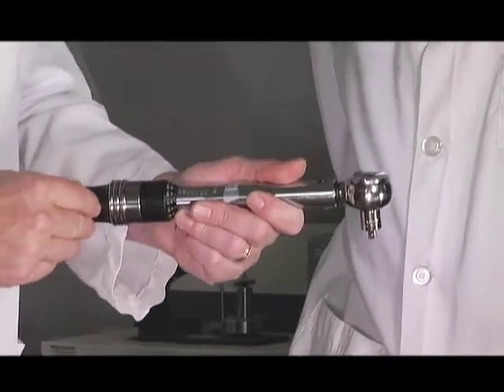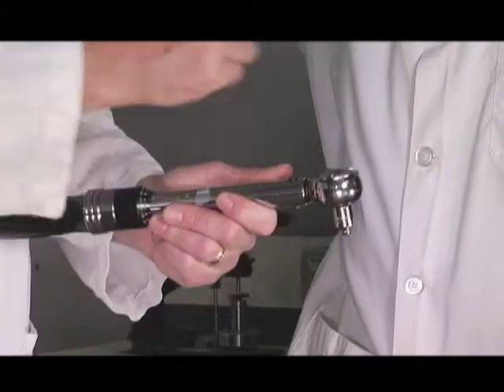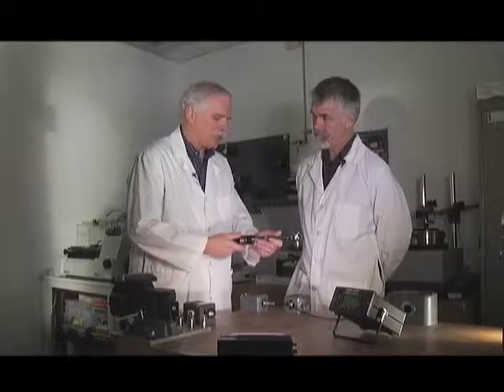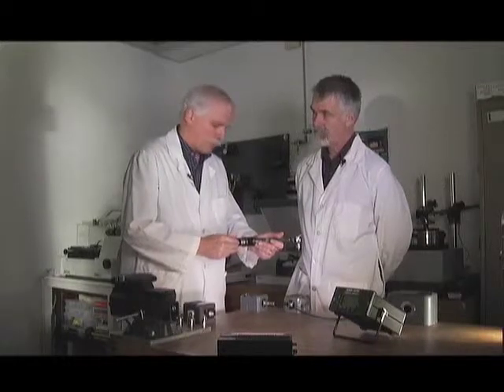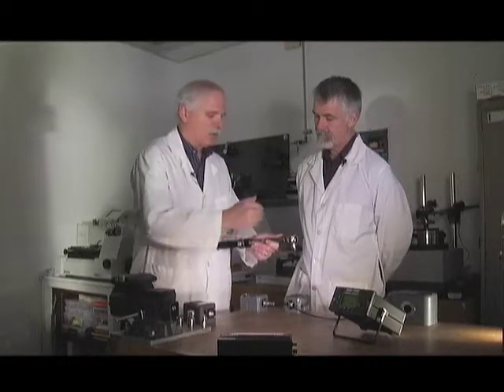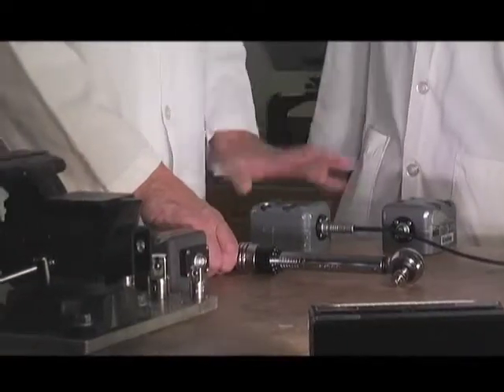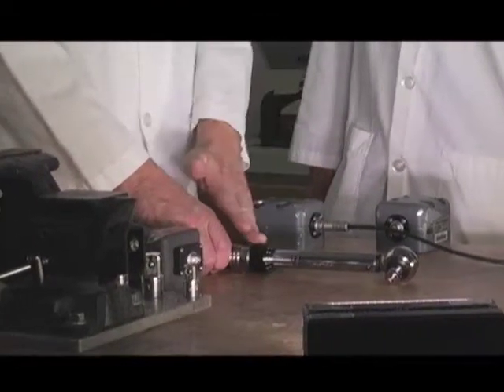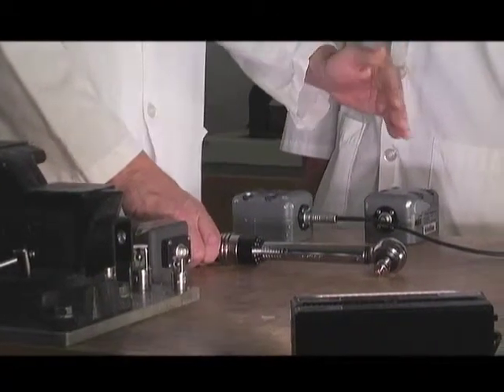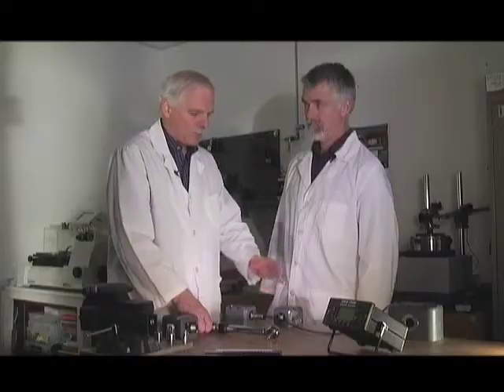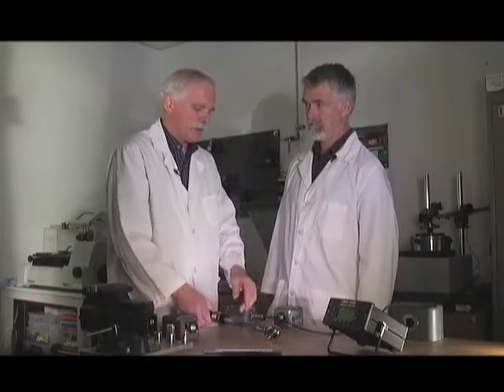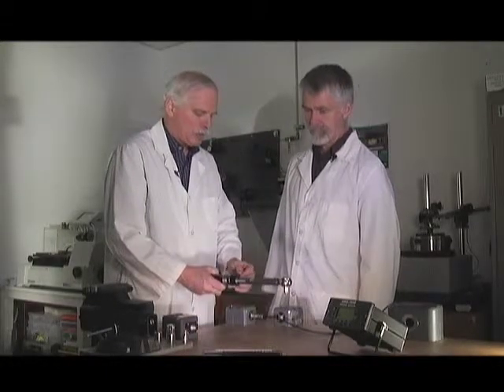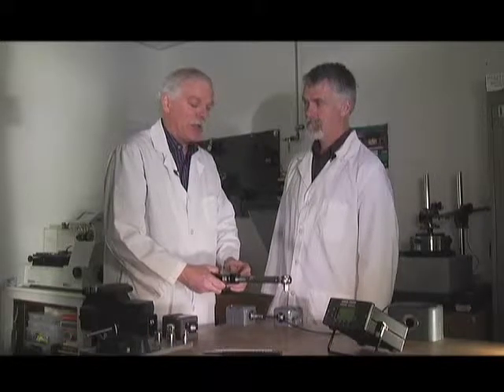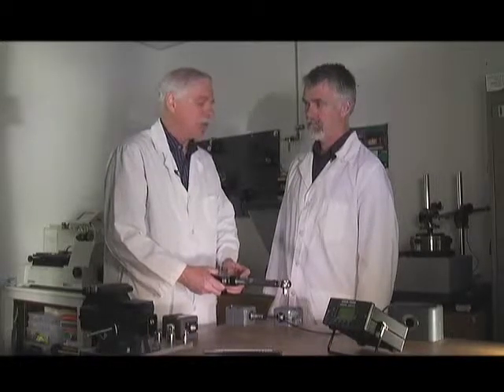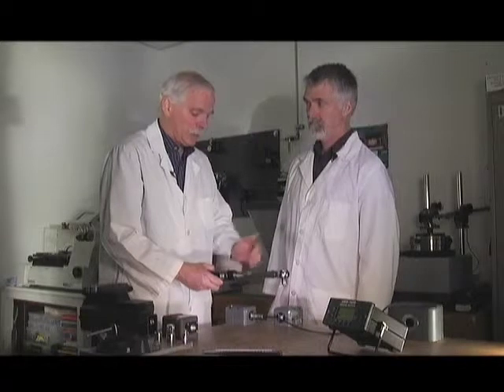This is a 0 to 250 foot-pound or inch-pound torque wrench, and you never check below 20%. These torque wrenches are designed to be used 20% to full scale. Now I'm set up on the lower range transducer, and we're going to check this torque wrench at 5 different points throughout its travel, starting at 20%, then 40, 60, 80, and 100% of its range. Okay. These torque wrenches are designed to be used at minimum. The lowest setting you could use is 20% of its range.